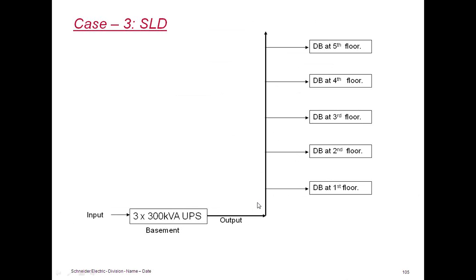The problem in this particular case was that they had an earth leakage relay at the output of the UPS. It was set to 30 milliamperes for safety purposes. The ELCB was tripping at least once in a month, approximately once in a month. The ELCB trips whenever the leakage current from the ground coming back to the earth leakage relay exceeds the 30 milliampere set value.